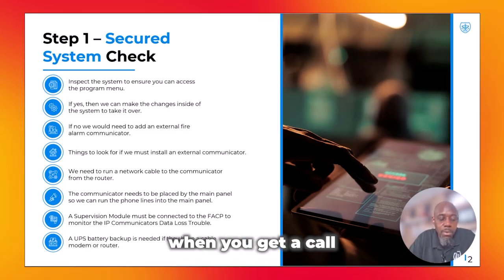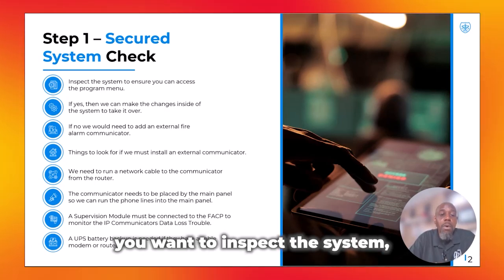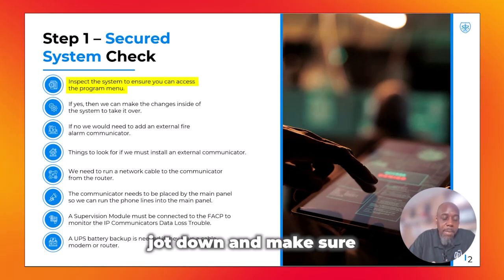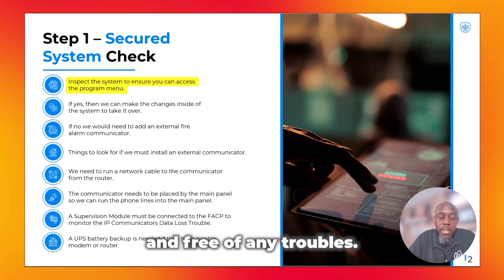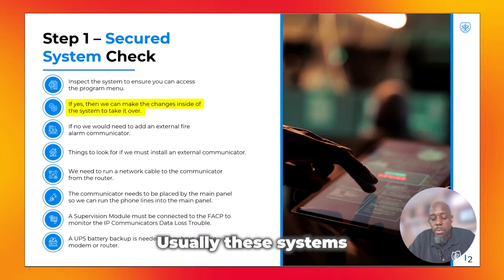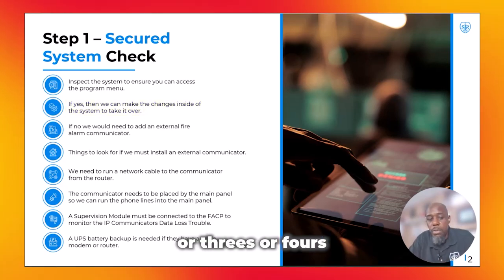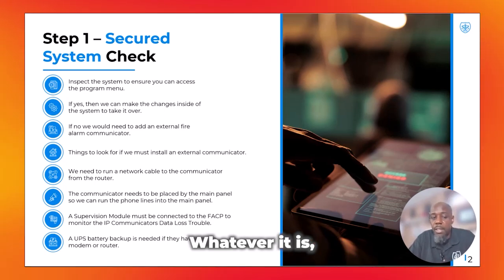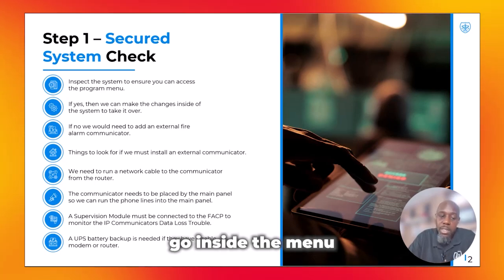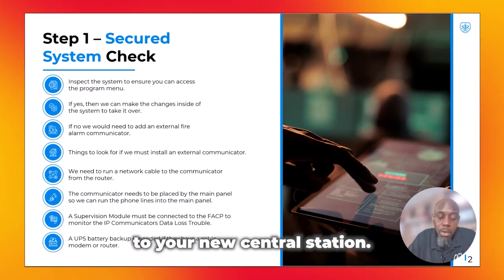The first thing you want to do when you get a call from a customer to check a fire alarm system for new activation is inspect the system. Make sure there are no existing troubles and the system is clear. Then make sure you can get into the program menu — usually these systems have a default password like 2s, 3s, 4s, 1s, 0s, or 6s. Once inside, change the account number and receiver numbers to point those receivers to your new central station.